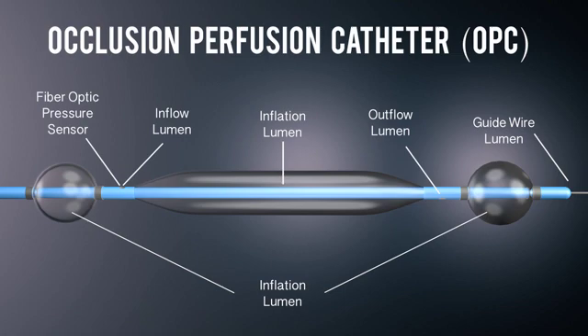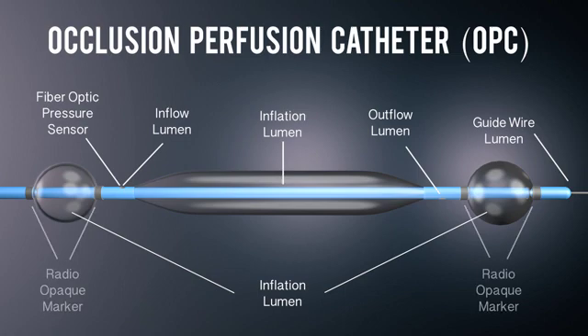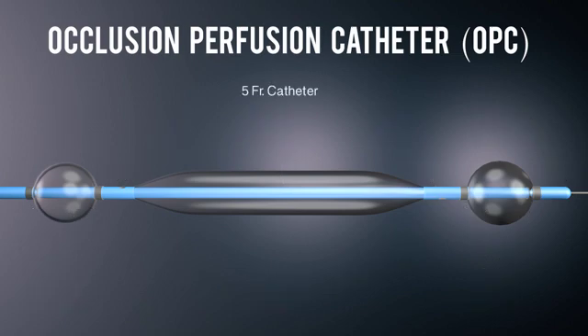A fiber optic pressure sensor is incorporated into the inflow lumen to monitor pressure within the treatment chamber. Radiopaque markers are located on both occlusion balloons to define the treatment chamber. The OPC is a five-french catheter compatible with a six-french sheath.